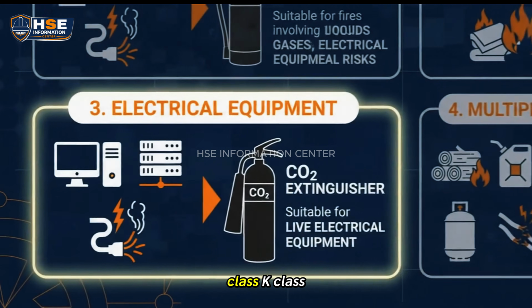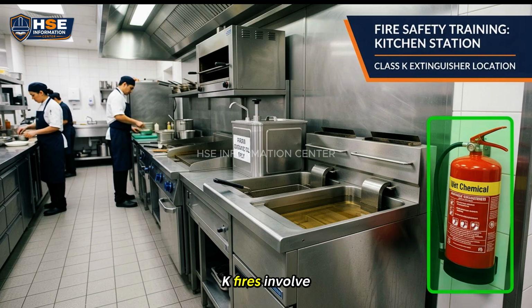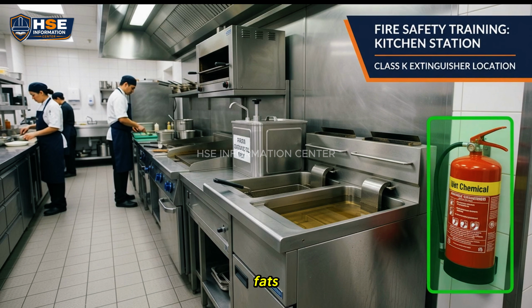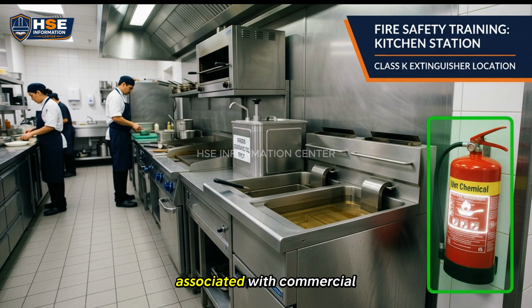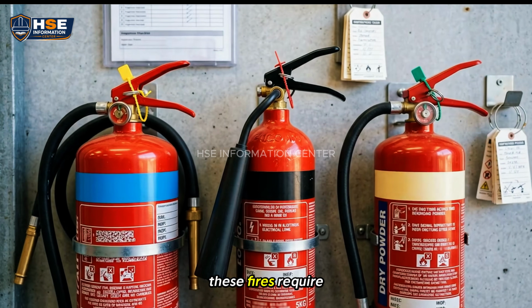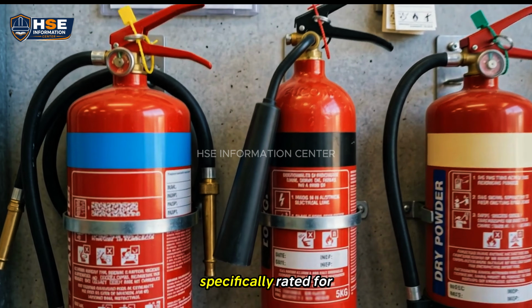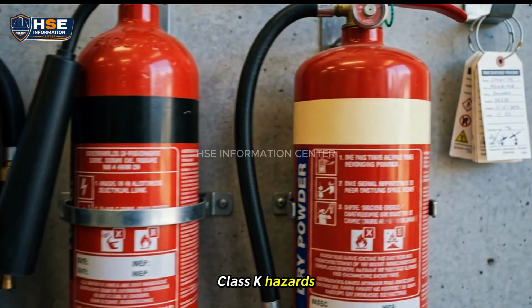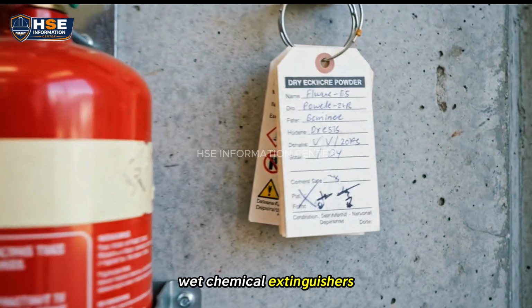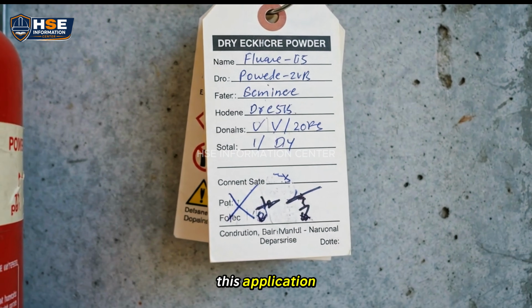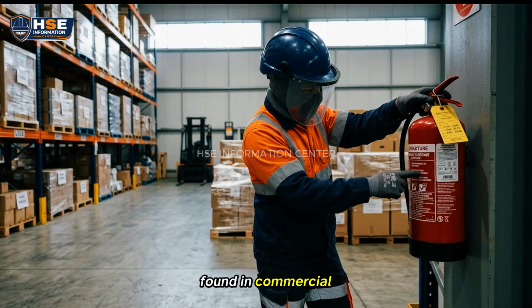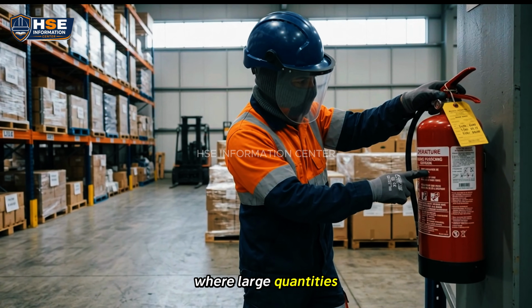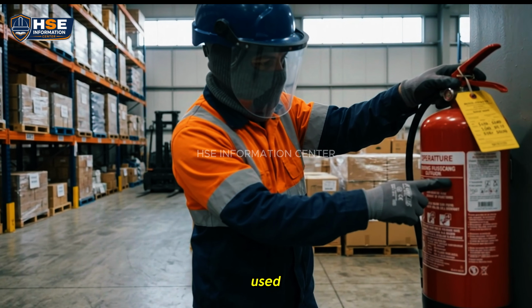There is also Class K. Class K fires involve cooking oils and fats. They are mainly associated with commercial kitchens, deep fat fryers, and similar cooking operations. These fires require extinguishers specifically rated for Class K hazards. Wet chemical extinguishers are designed for this application. They are commonly found in commercial kitchens where large quantities of cooking oil or fat are used.